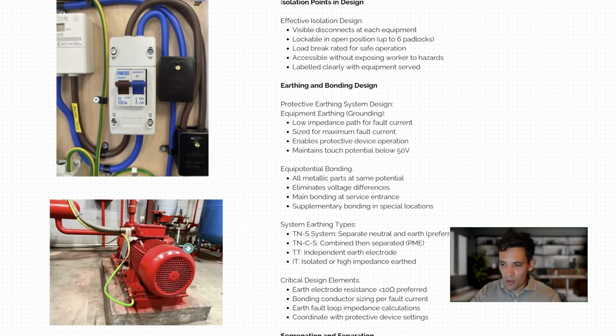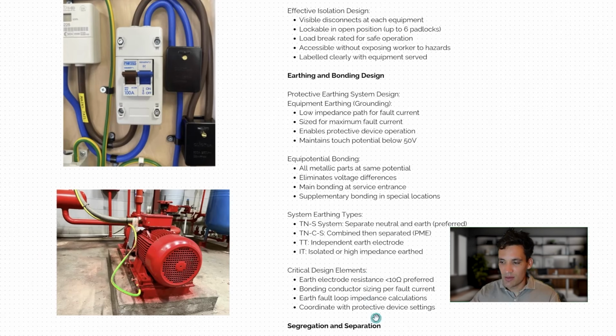All exposed metallic equipment that has power running to it needs to be bonded to earth, and this eliminates voltage differences between equipment and between different metallic surfaces. We spoke about the different earthing types, but the correct earthing type has to be chosen for the project, dependent on the fault currents, the system design, the layout. Critical design elements when we're talking about an earthing system will be the earth electrode resistance, which should always be less than 10 ohms, the bonding conductor size for the specific fault currents, the earth fault loop impedance and how that impacts circuit breaker sizing, and coordinating that with the protective device settings.